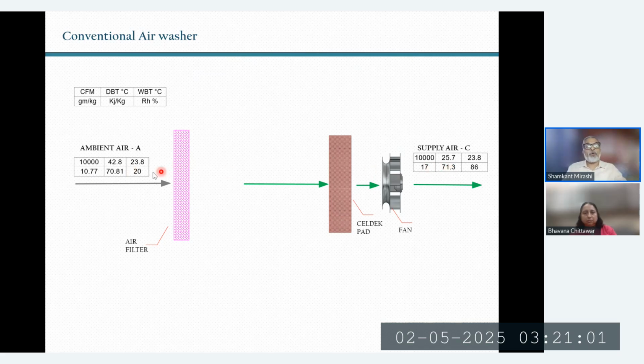But this is always limited by wet bulb - those who remember their thermodynamics know adiabatic cooling or evaporative cooling is limited by wet bulb. The approach is wet bulb, so we cannot cool that air below ambient wet bulb, though we do get substantially cold air. The only limitation is the dry air is now absolutely wet - almost 86% humidity, and if you see the grams of water, it's almost 17 grams. This is what evaporative cooling does.